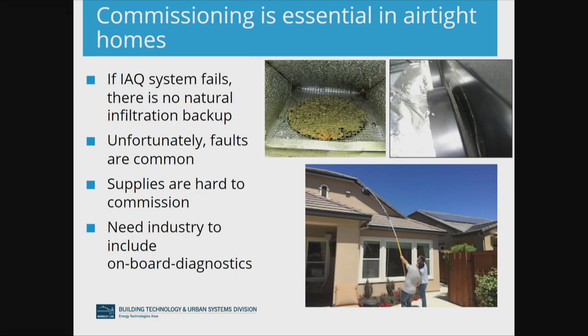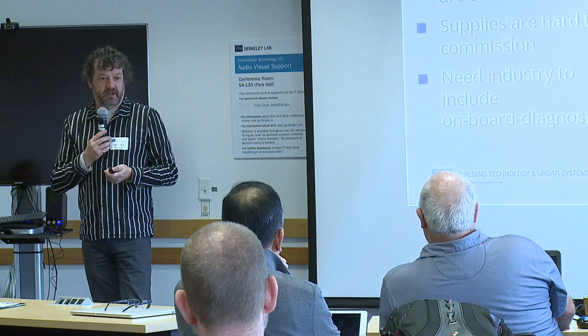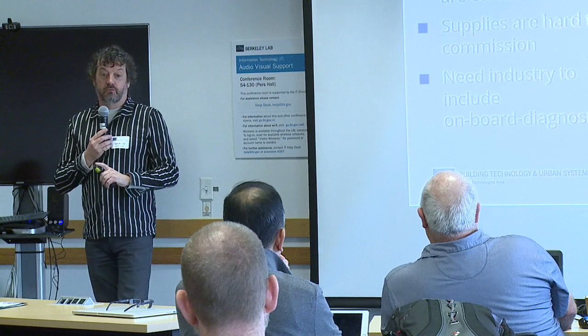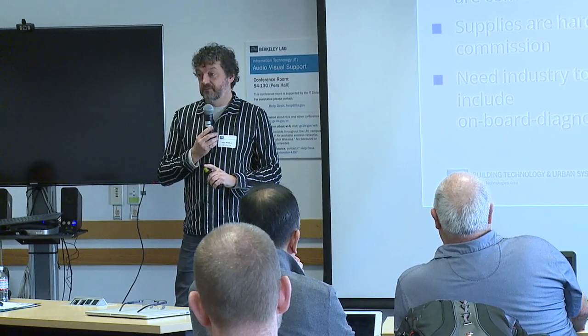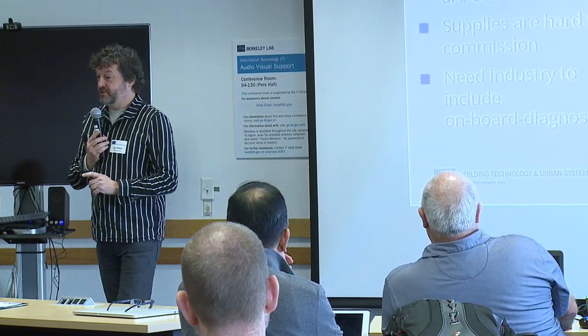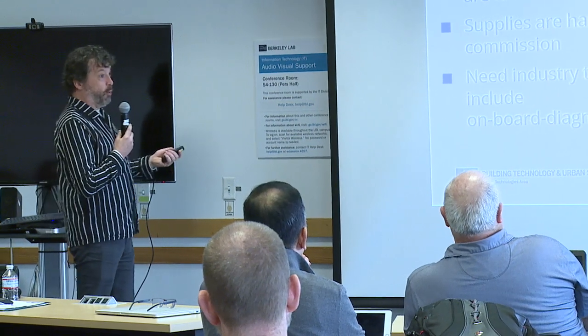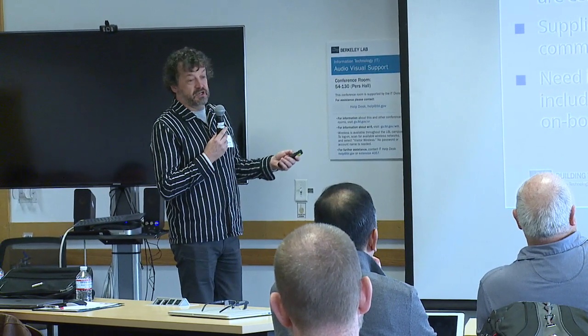At my leaky old house, if my exhaust fan fails, well, things will get a little bit worse, but it won't get terrible. If you're in a brand new, very tight building, not having ventilation is a crisis for you. So it's important—there's no natural infiltration backup.